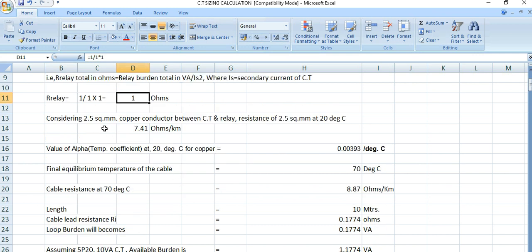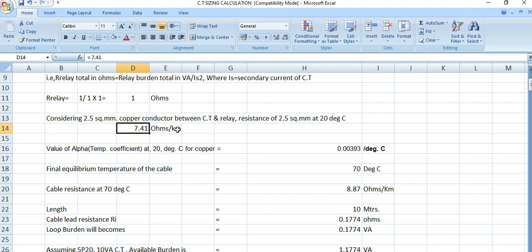Now, for the connecting lead resistance, we are considering a 2.5 square mm copper conductor between the current transformer and the relay. The resistance of 2.5 square mm copper conductor at 20°C is 7.41 ohms per kilometer — this value can be obtained from any standard or cable manufacturer's catalogue.